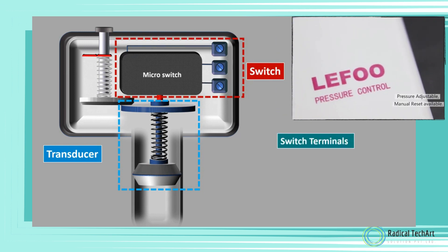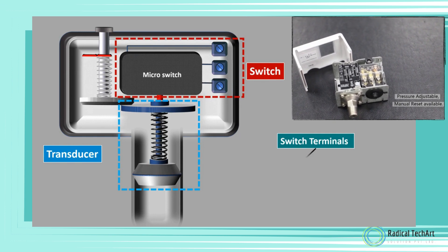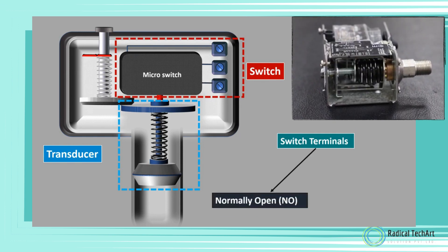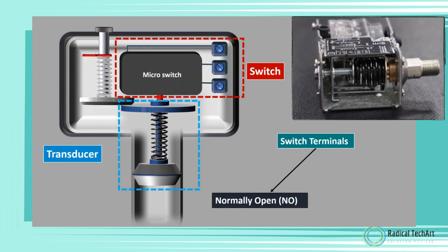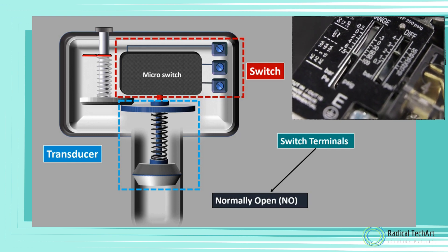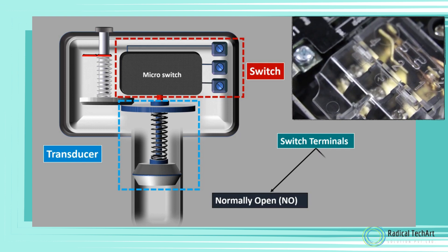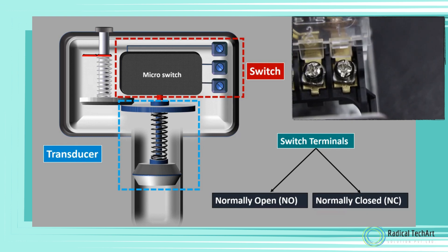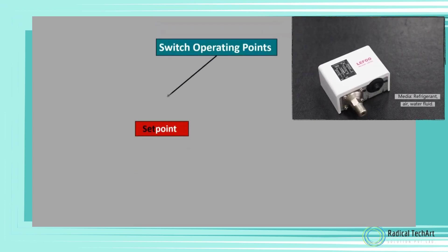Some switches have the switch terminals open when no pressure is connected, which is called normally open switch (NO). When enough pressure is applied, the switch closes. On the other hand, some switches have the switch terminals closed when no pressure is connected, which is called normally closed switch (NC), and when enough pressure is applied, the switch opens.